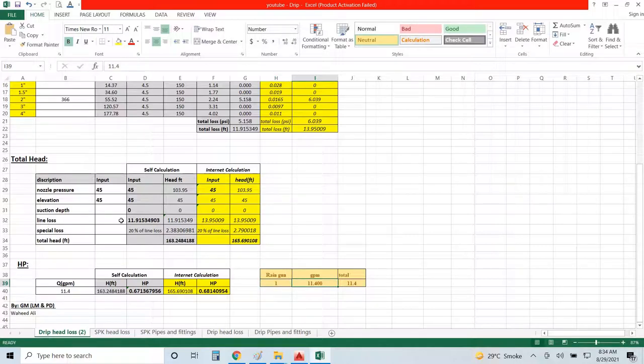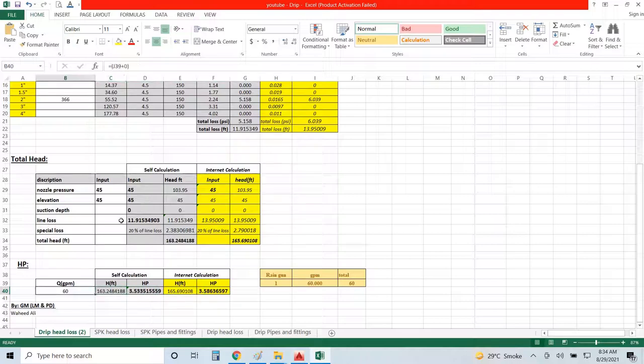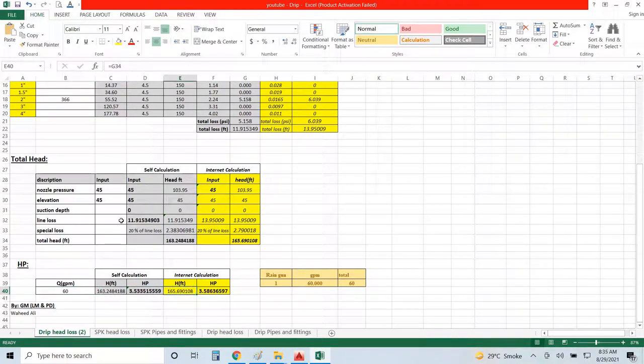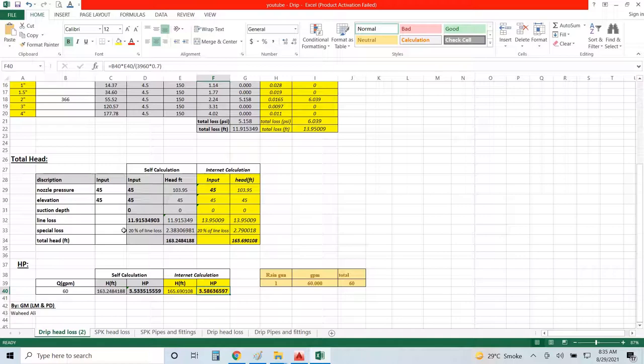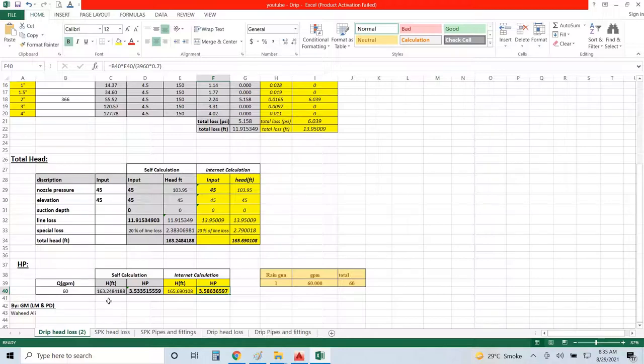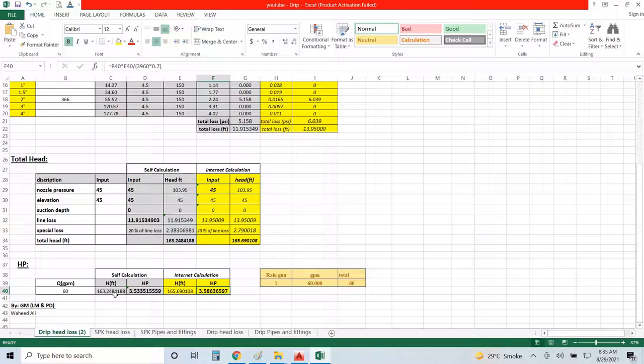These are line losses and everything. I have now a rain gun here, that is one, and it is drawing water 60 gallons per minute. So according to this calculation, I have to select a pump about 3.5 horsepower. But when you go to the market, you will ask for a pump which can withdraw water at 60 gallon per minute at 163 feet head.